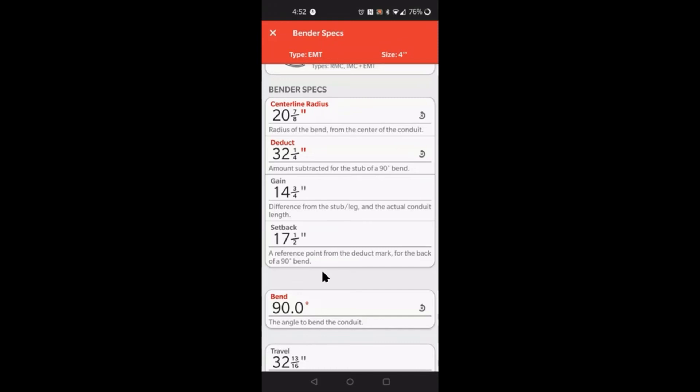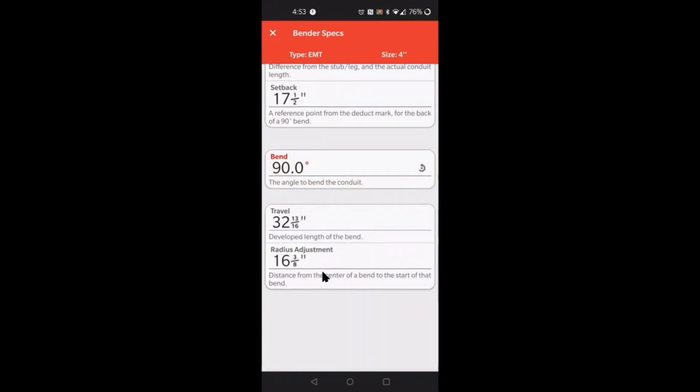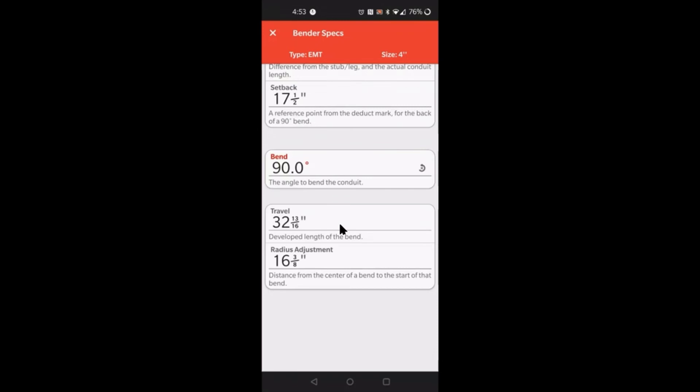Moving right along, you have the 90 degree bend here and the travel for the 90 and the radius adjustment for that 90 degree angle. Basically what you would use the travel for is basically it says the develop length for that bend. But a way to use that travel value is, let's just say you're not using a digital level or protractor, you can use this value here to make the 90 degree bend. You simply just mark it twice, once on the conduit and then directly across from that mark you want to mark it on a point on your bender so that you can see when you start bending it as that conduit moves forward, so does that mark.